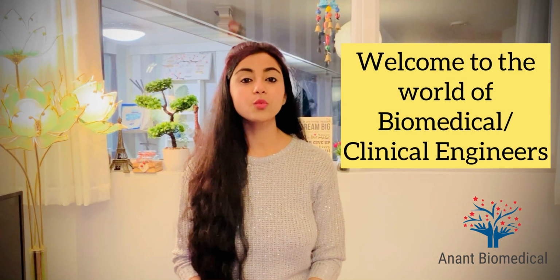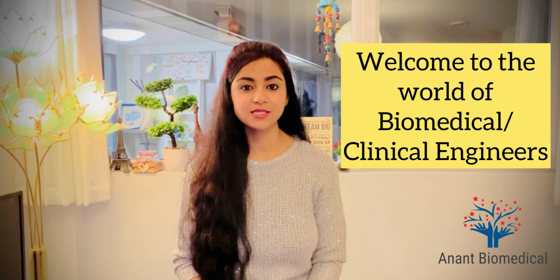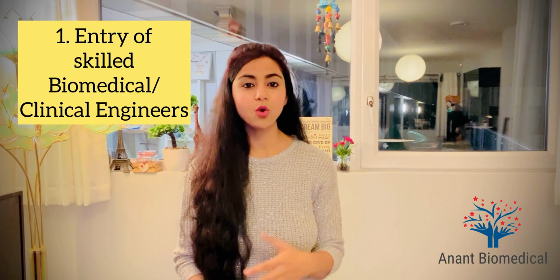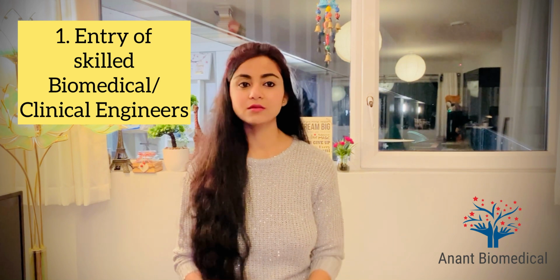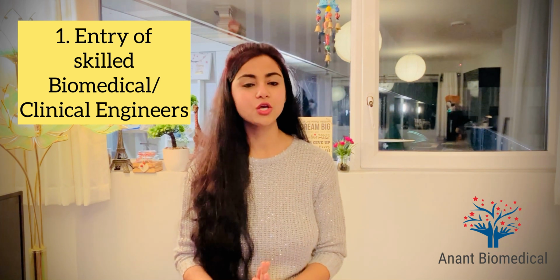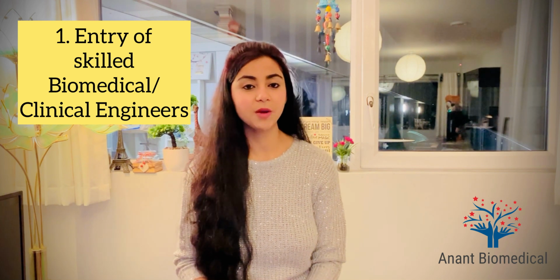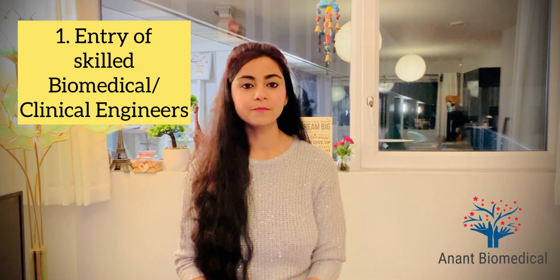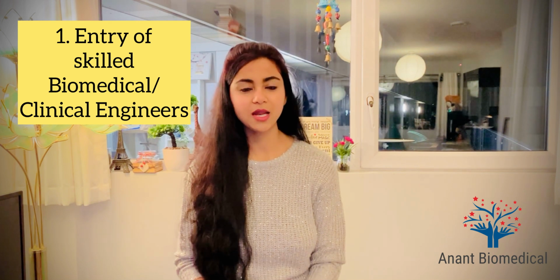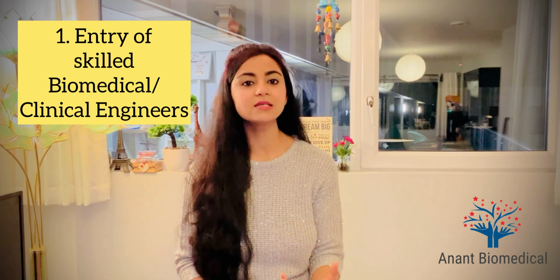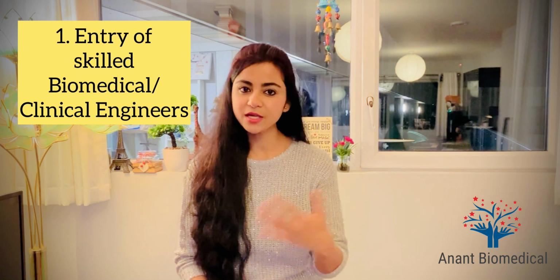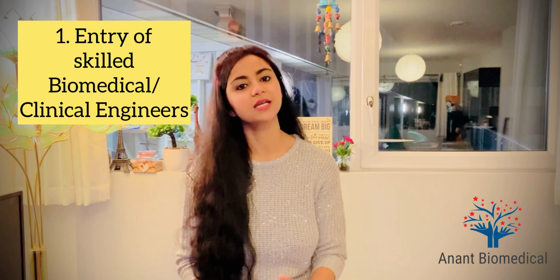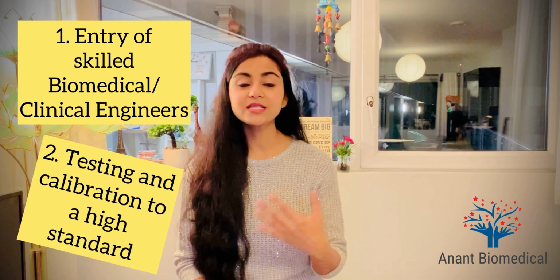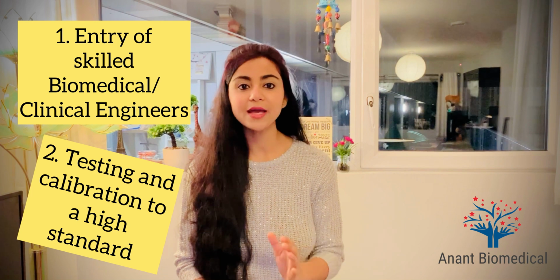So let's talk about what happens behind the scenes with these medical devices that are used on us to make sure that they are reliable at the point of use. What happens is, ideally, a biomedical or a specialist clinical engineer, and they can be either from within the hospital, so they can be from an internal clinical engineering department, or they can be outsourced as well. They are invited to visit the hospital and the particular department which needs the medical devices to be tested and calibrated, and they are told about which medical devices need to be tested and calibrated. Secondly, they test and calibrate these medical devices to a high standard.